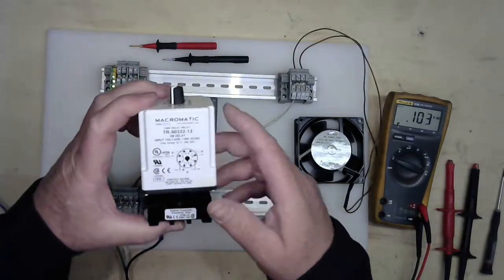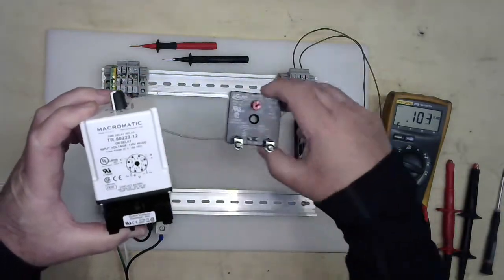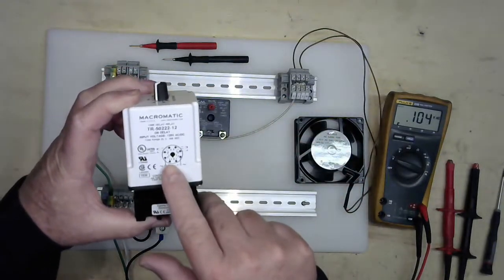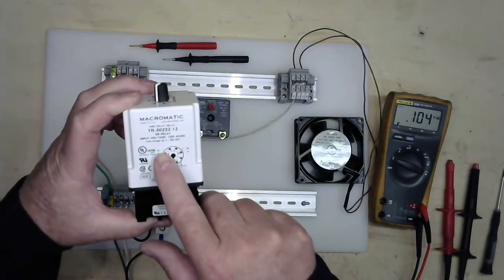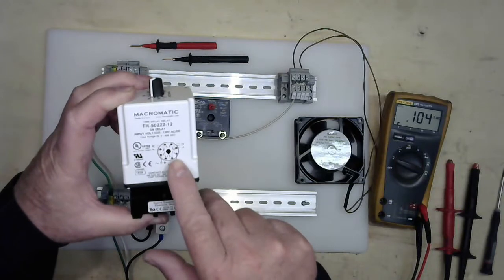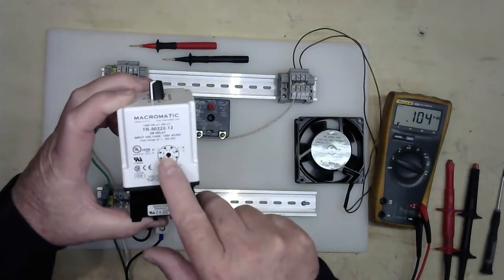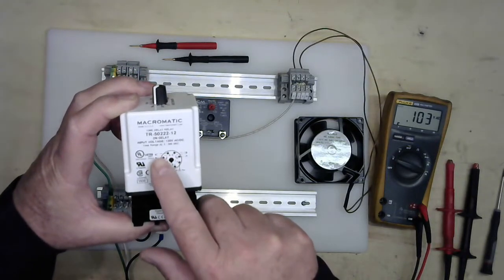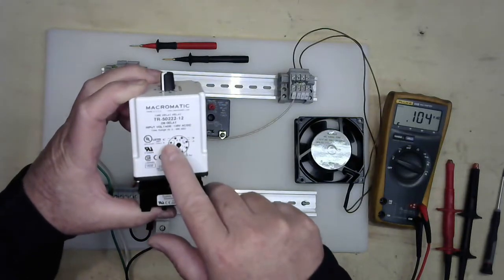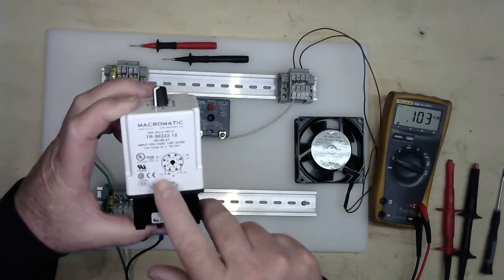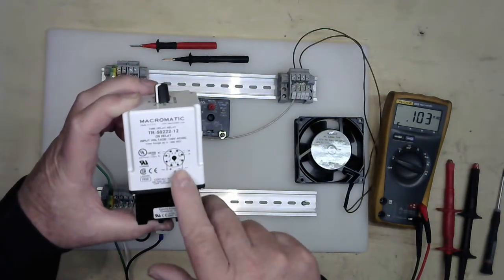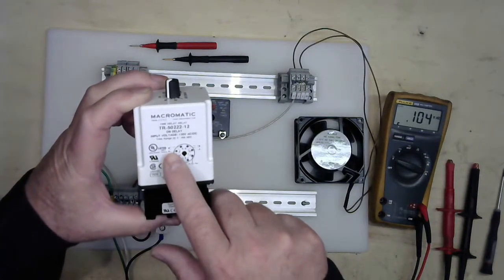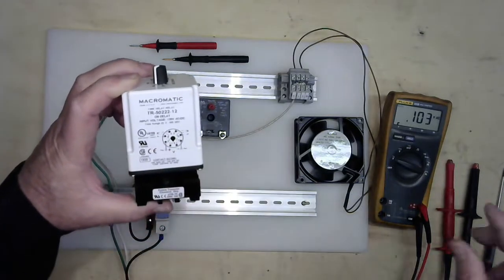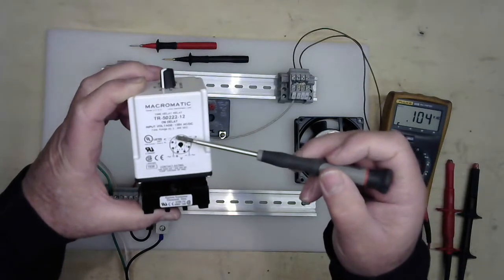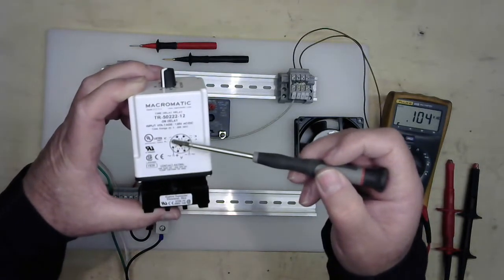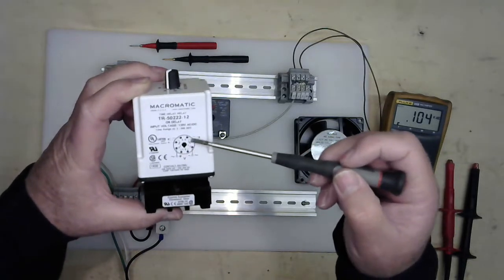This particular one here has a little different setup than you have here. We have our common contacts, two of those. The common contact will go to a normally closed contact, and the common will go to normally open. Same thing on the reverse side. When our common has applied voltage, it will make contact to our normally closed contact, allowing that circuit to operate. Once the timer coil is receiving the nominal voltage, the timer will start timing out, after which time it will change the contacts from normally closed to normally open. Once our common goes from our normally closed to our normally open after the timing process, our timer will time out.